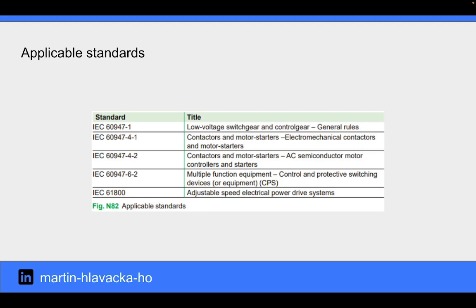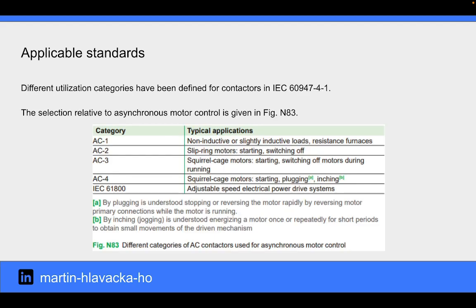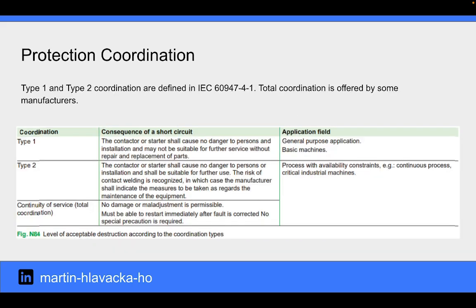On this slide, the different applicable standards are listed in the table. Different categories of AC contactors used for asynchronous motor control have been defined in IEC 60947-4-1. Protection coordination. Type 1 and Type 2 coordination are defined in IEC 60947-4-1. Total coordination is offered by some manufacturers. On the table, you can see the level of acceptable destruction according to the coordination types.